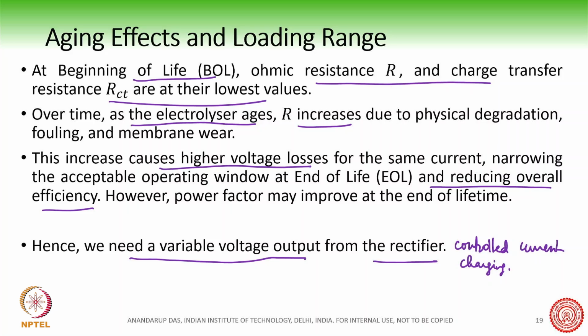The most important topology as of date is the thyristor-based electrolyzer rectifier. These are the most important rectifiers used, usually taken from medium voltage, or sometimes low voltage, because we need megawatt-level power from the grid fed into the electrolyzer. Often we take it from medium voltage and inject thousands of amperes of current through the electrolyzer. This is one more application of a PWM rectifier or a line commutated rectifier.